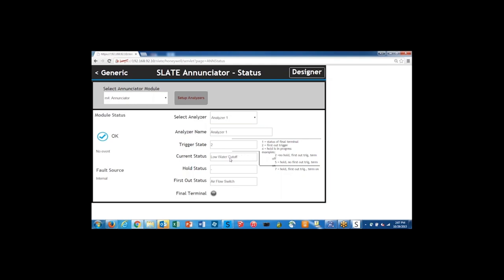Now our low water cutoff is not made, so we turn that back on. It'll cycle quickly through the high temperature limit. Once it checks to make sure that everything is okay, then we get our interlocks proven message and we get a green light on our final terminal.